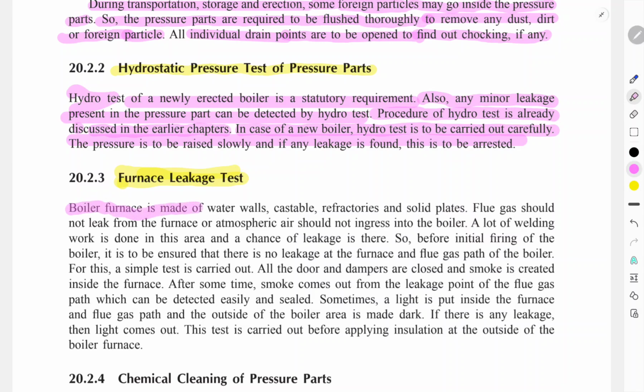So the boiler furnace is made of water walls, refractories and solid plates. Flue gas should not leak out of the furnace, and atmospheric air should not ingress into the boiler. A lot of welding work is done in this area, and the chance of leakage is there. So before the initial firing of the boiler, it is to be assured that there is no leakage in the furnace and flue gas path of the boiler.